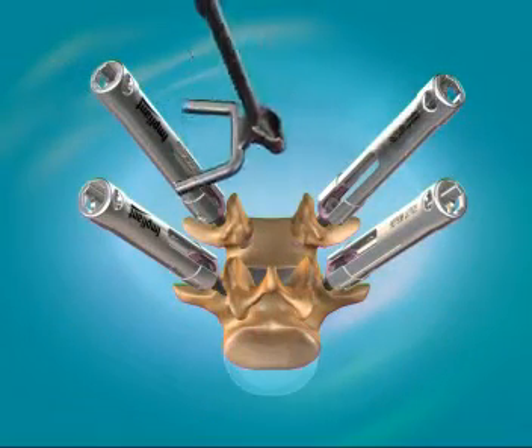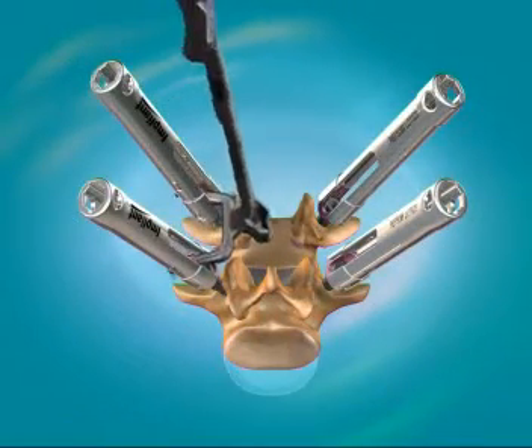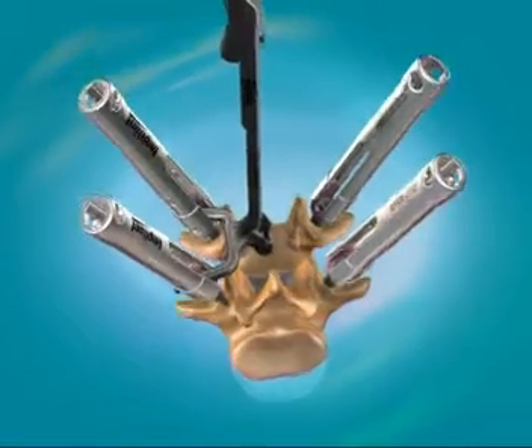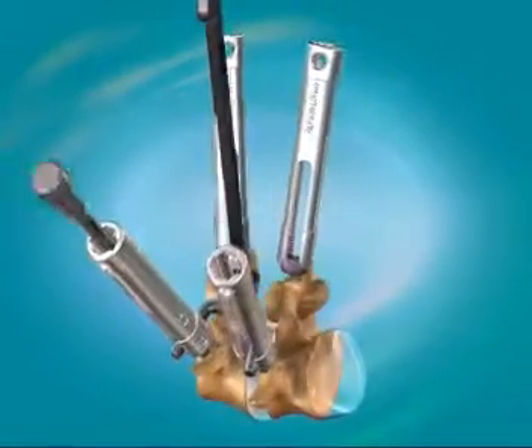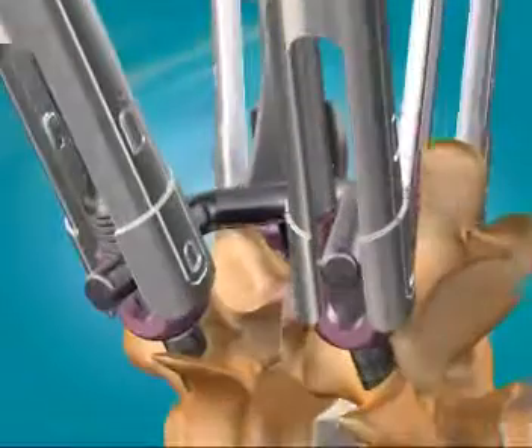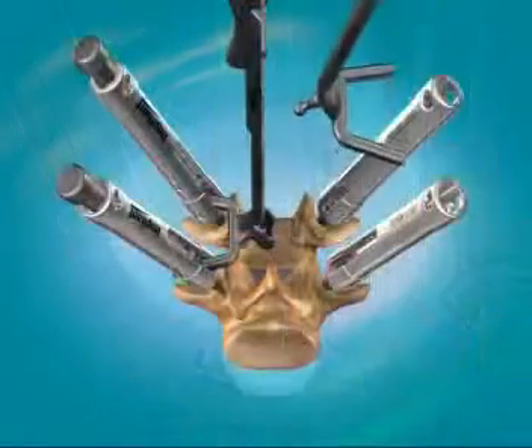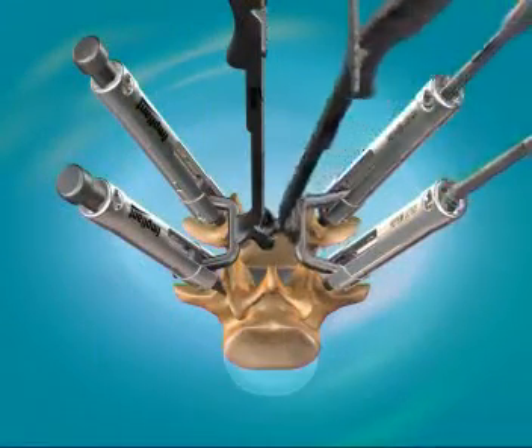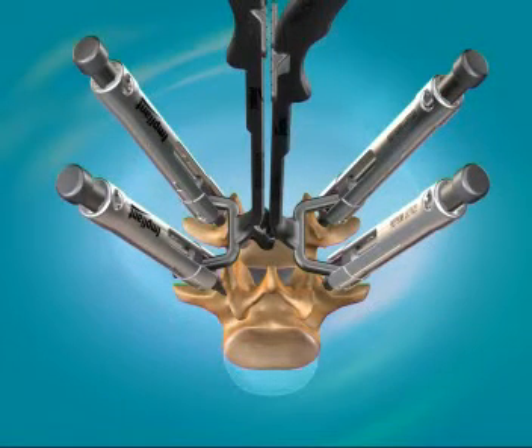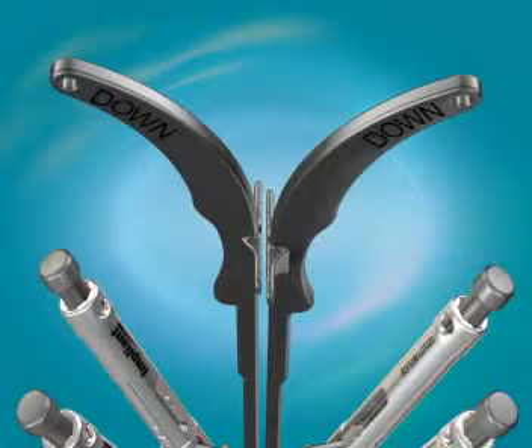First, take the female half of the gauge and insert it into the pedicle screw heads. Insert 2 temporary set screws to lock the gauge in place. Insert the male half of the gauge into the pedicle screw heads. Insert 2 temporary set screws to lock the gauge in place. Again, verifying proper up and down orientation. Confirm that you have matched the proper gauge for the specific vertebrae.